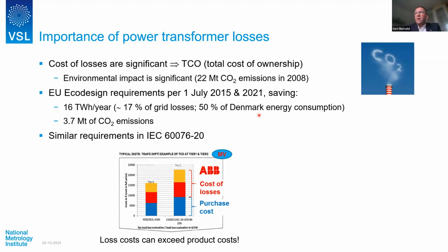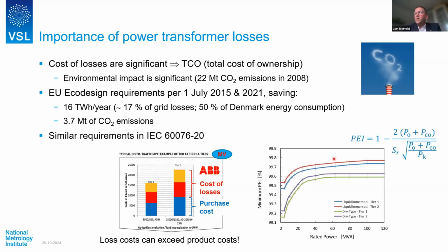And actually, there is a certain table, they call it the peak efficiency index, with a particular calculation. I won't go into the details, but you see here in the graph, as a function of the rated power in MVA of the power transformer, there is a certain minimum peak efficiency index. And that is not only an EU requirement, but similar requirements are now also part of the IEC 60076-20 series, where they also mention requirements on efficiency.